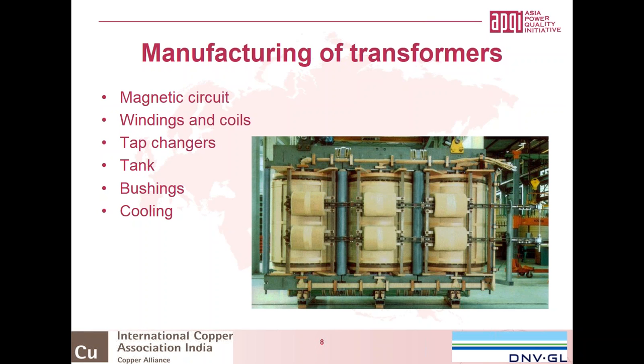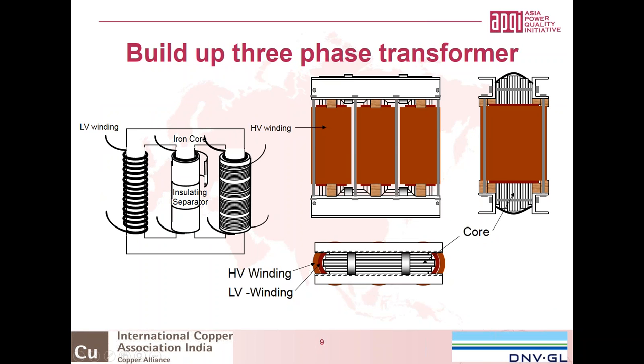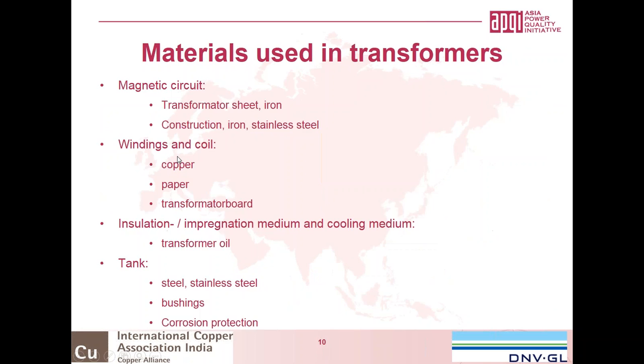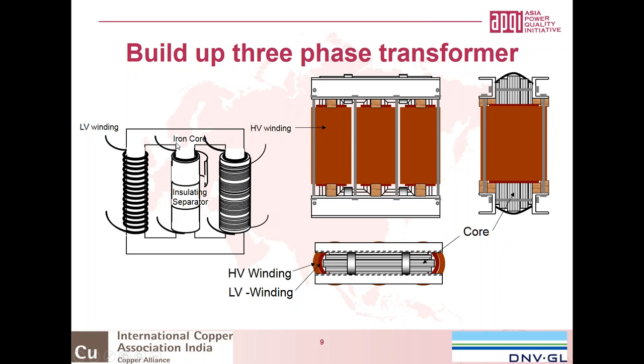If you look at the build-up of a three-phase transformer, I would like to show you, going from the picture on the left side, where you will see the core, which is a three-phase core, and also you will see that there is a low voltage winding on one core. On the next one, after the low voltage winding, normally they will have a kind of insulation separation, because on the outer side of the windings you will normally find the high voltage winding.